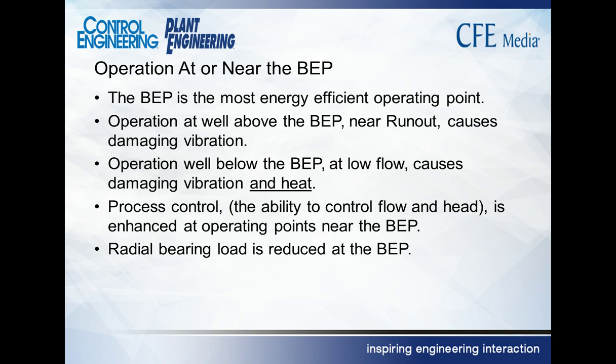I'm not going to read you this slide, but take a second and read through that. The impact of being very far away from the best efficiency point is going to have an impact not only on your efficiency but also on the reliability of the pump. I noticed that last point there, even the radial load on the bearings is increased as you get away from the best efficiency point. Anyone have questions on that?